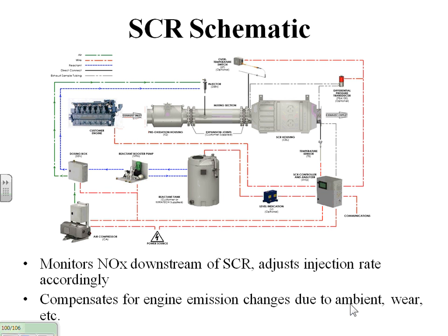Let me back up. The EPA is requiring that you either have a certified engine today, which no manufacturers do, or if that's not possible, they say we'll accept an EPA compliant engine. Well, what that is is an aftermarket supplier, and there are several of them out there that will sell you components.